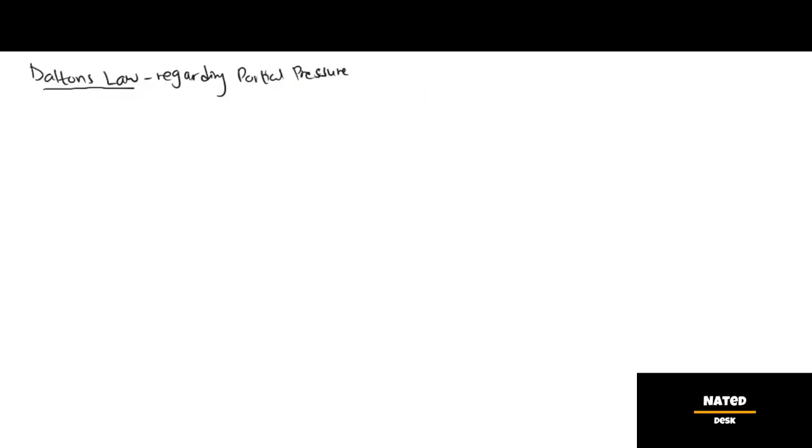The law states that the pressure exerted by mixture of gases or vapor is equal to the sum of the individual pressures of each gas. It can be written as an equation which says absolute condenser pressure P equals the steam pressure PS plus partial pressure of air PA.